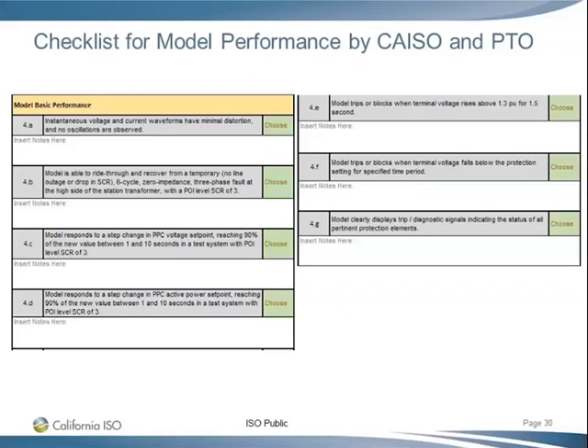To summarize the tests here: instantaneous voltage and current waveforms have minimum distortion and no oscillation. So this needs to be yes. Model is able to ride through and recover from a temporary fault. This one says 6 cycle. Actually, I think that's not right. Most tests are 4 cycle. We can correct that. 4 cycle, 0 impedance 3-phase fault at the high side of the station transformer. I think this description might be a little bit off. We apply that at the POI with SCR equal to 3, but it's not at the high side of the station transformer. It is at the other end of the gen tie. So this has to be answered yes.